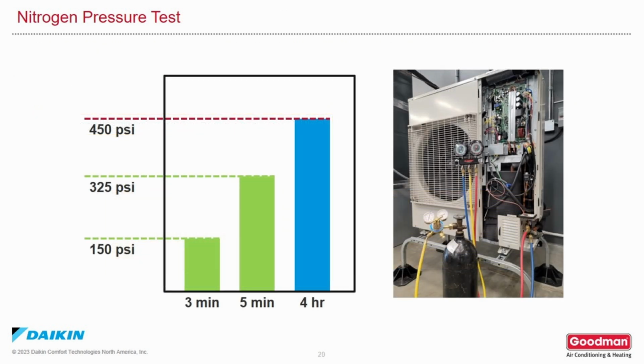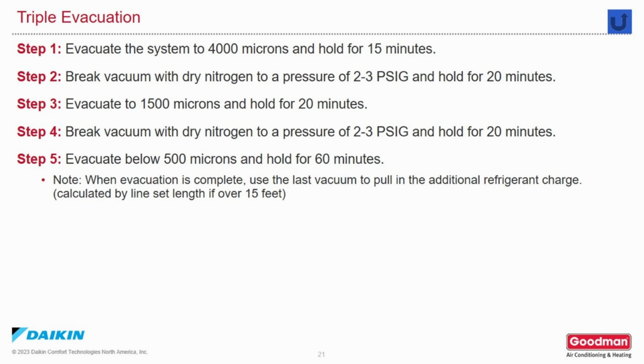When charging the system with nitrogen for a pressure test, do it in increments to ensure the integrity of your braze connections. Charge to 150 psi, allow that to remain for approximately 3 minutes. Then, increase that charge to 325 psi, allow that to sit for approximately 5 minutes. Then charge the system to 450 psi, or whatever you choose as a high pressure test. Overpressurizing the system could cause dry nitrogen to leak past the service valve into the refrigerant circuit of the outdoor unit, contaminating the refrigerant.